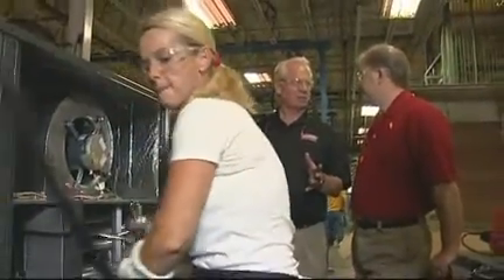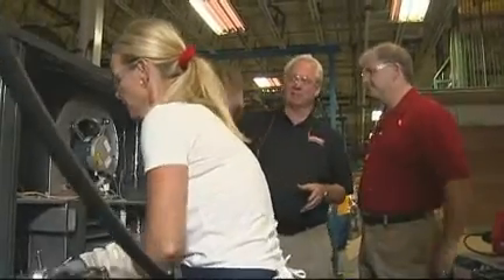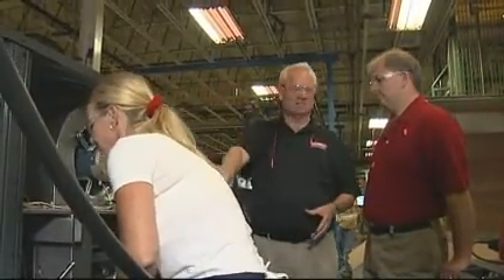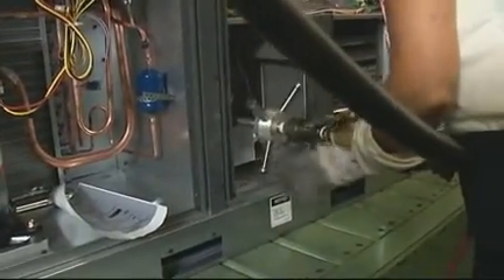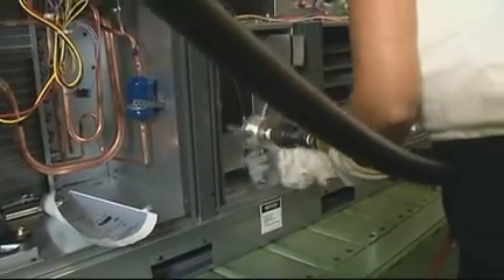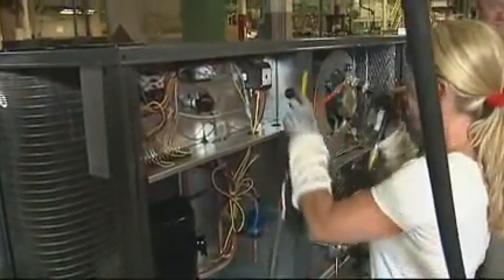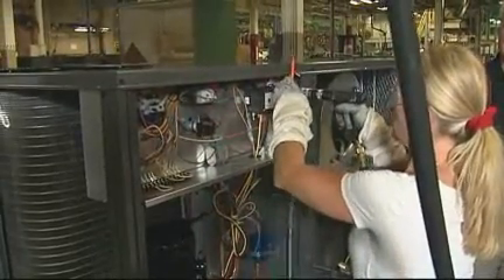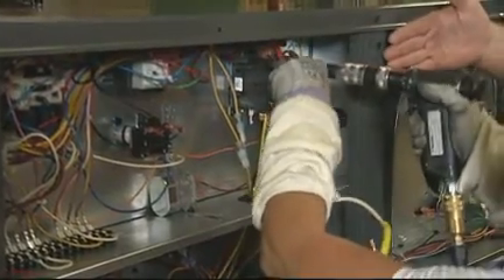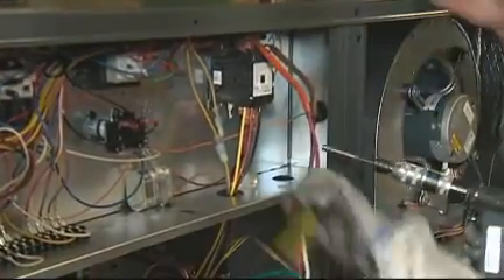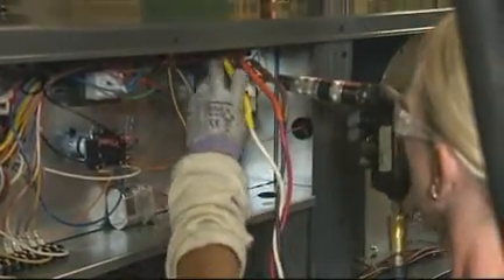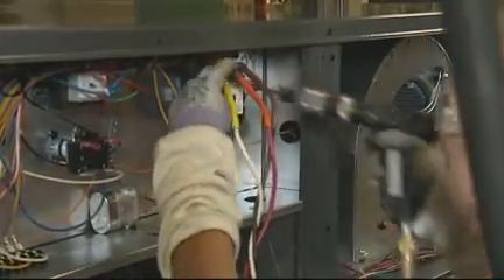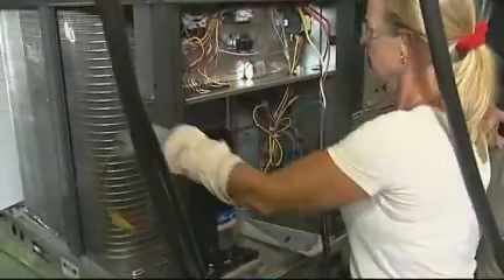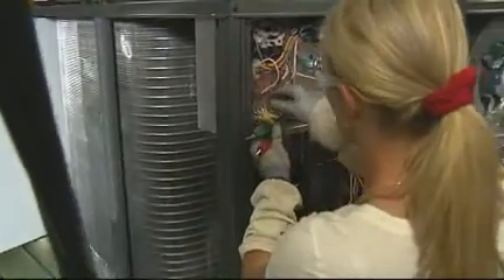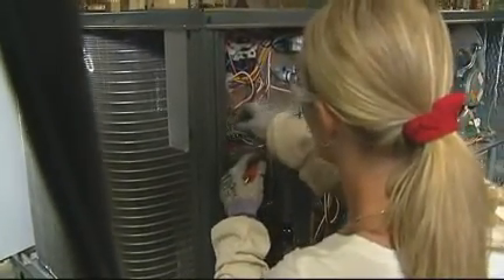Sure. Customers told us one of the big problems they had with other designs is you had the control panel on that side, everything else on this side, so you'd activate on that side, come around on this side to see if it worked. Now she's hooking up the gas line. Now she's hooking up the high voltage electrical. Of course, there's no power to those lines right now. And you'll notice on the contactor, another thing our customers told us, they like lugs. They don't like other types of electrical connections. Those provide very positive electrical contact for the incoming electrical lines. Next, she'll hook up the low voltage connections that provide information from the thermostat.